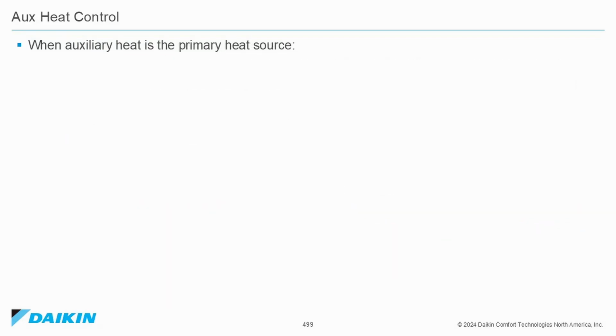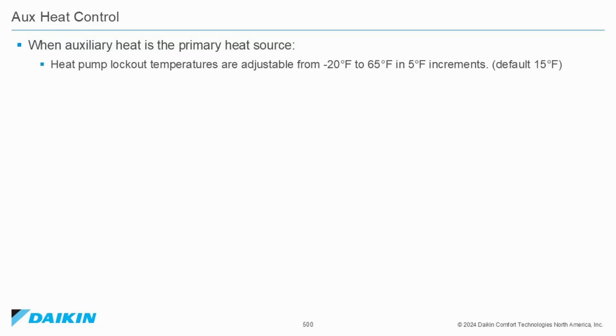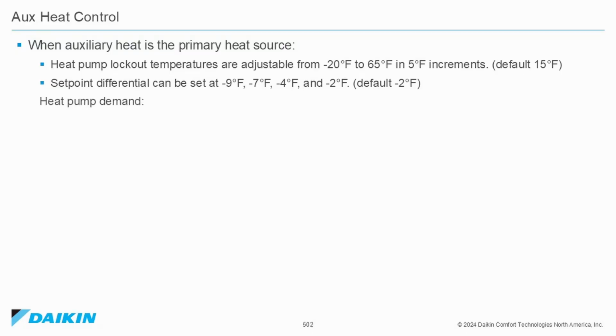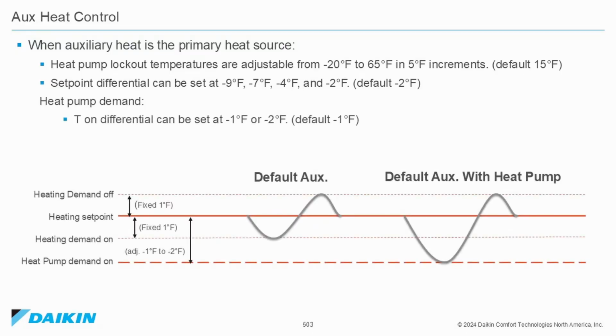When auxiliary heat is the primary heat source, heat pump lockout temperatures are adjustable from -20 to 65 degrees Fahrenheit in 5-degree increments. Default, 15 degrees Fahrenheit. Set point differential can be set at -9, -7, -4, and -2 degrees Fahrenheit. Default, -2. Heat pump demand. T-on differential can be set at -1 or -2 degrees Fahrenheit. Default, -1. T-off differential is fixed at 1 degree Fahrenheit.